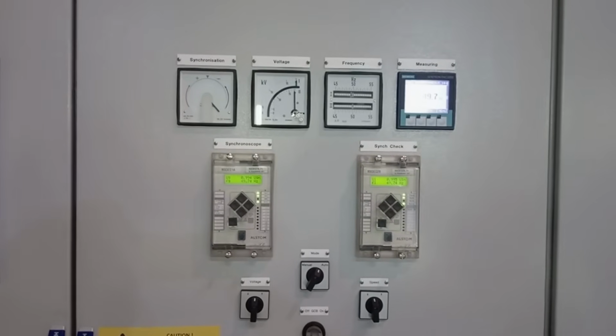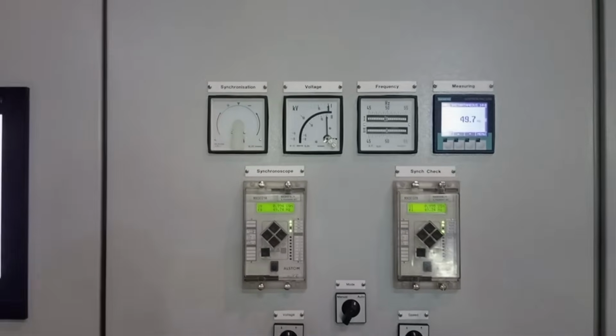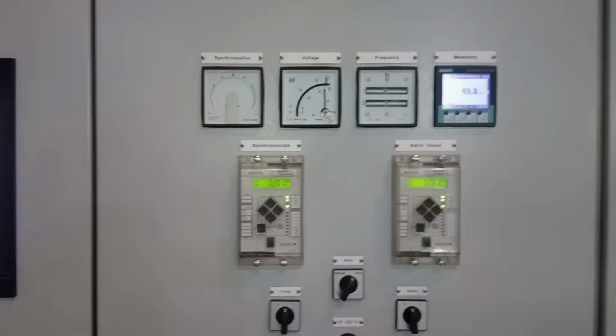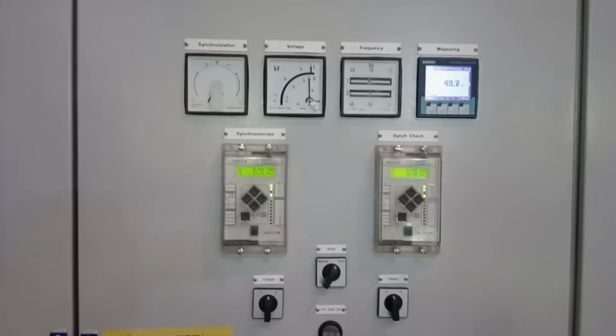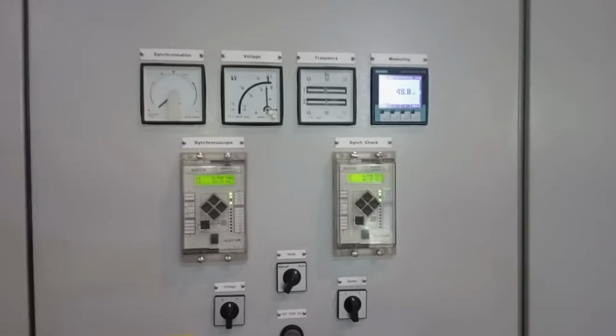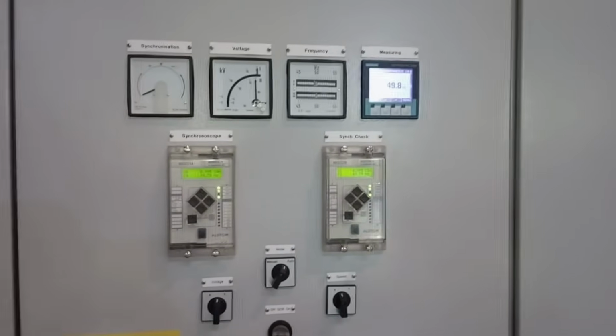Before synchronization, three things must match perfectly: voltage, frequency, and phase angle. The turbine governor adjusts speed to match grid frequency. The AVR adjusts excitation to match voltage.